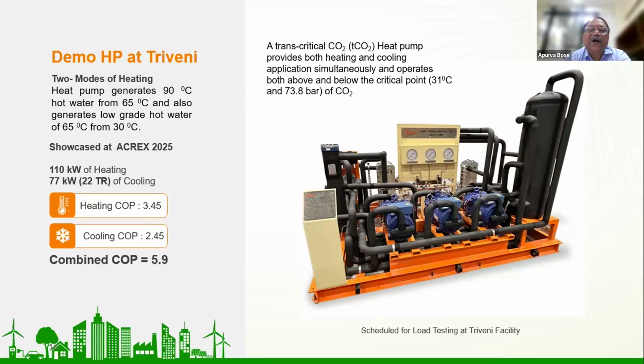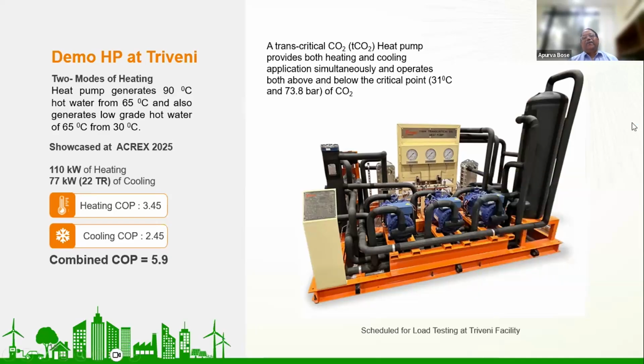CO2 as a fluid has a unique property: its critical point is 31 degrees Celsius and 73.8 bar. Beyond this, it is in a supercritical stage; below this, it is in a subcritical stage. If we use both phases of this fluid, it moves between supercritical and subcritical, and because of this, the outcome we get through the heat pump is heating and cooling.